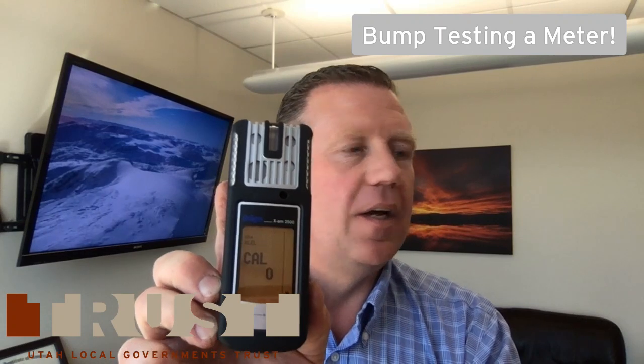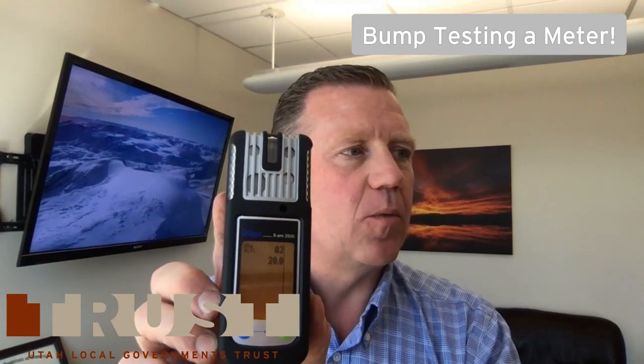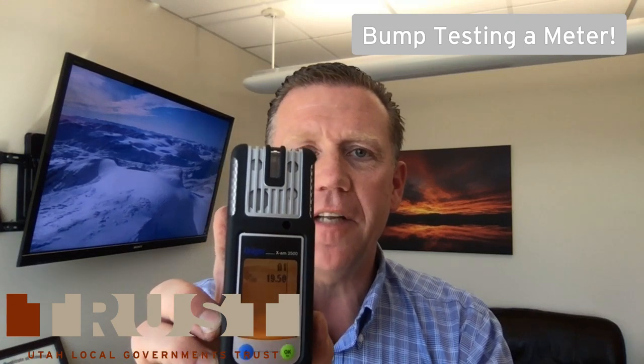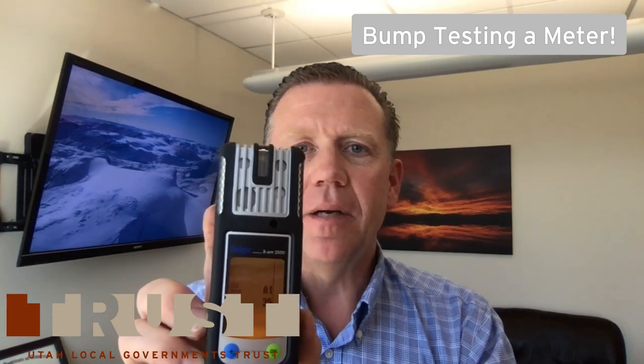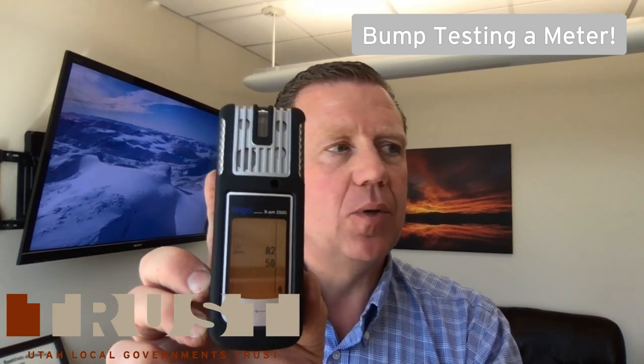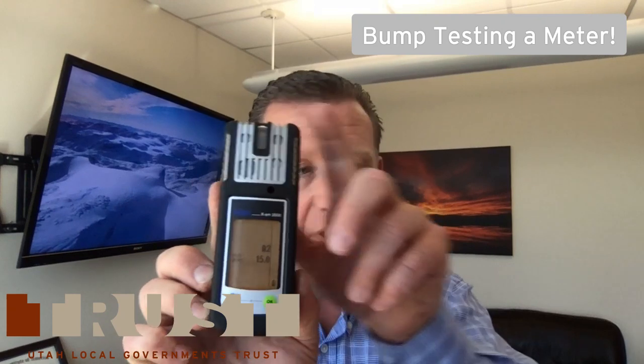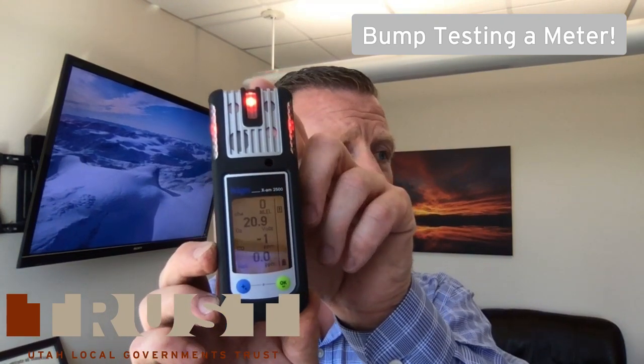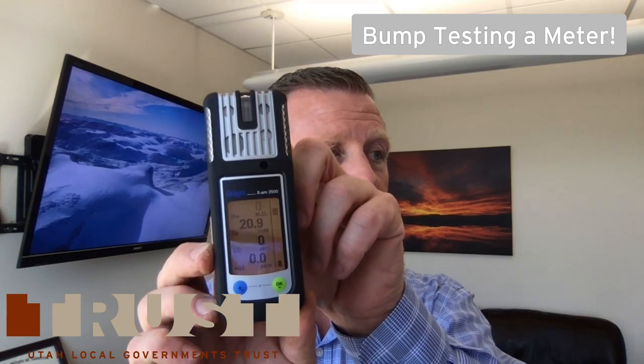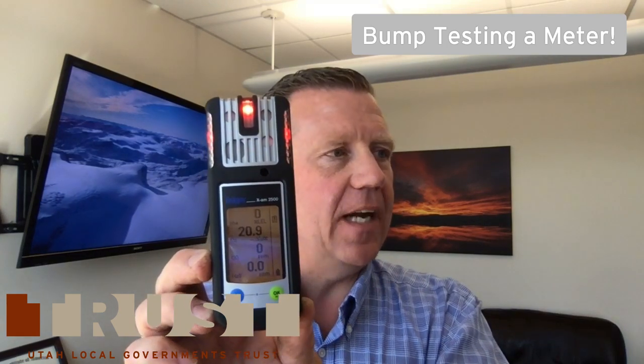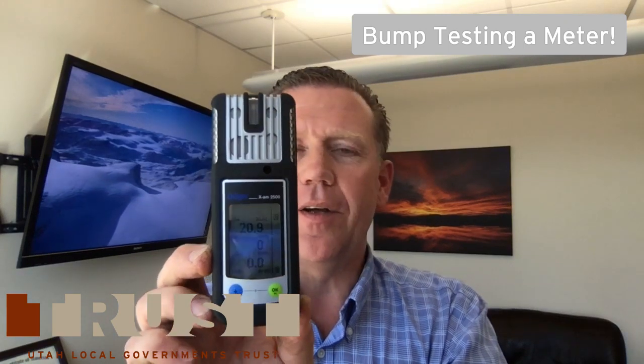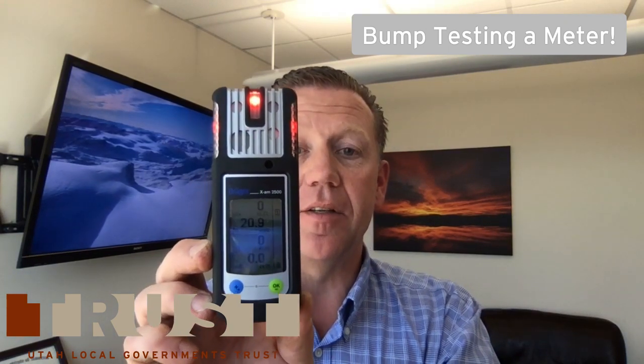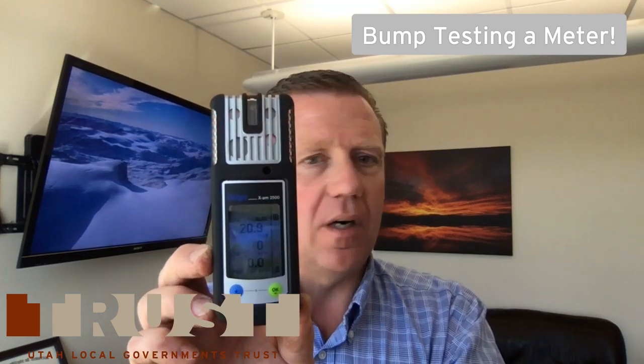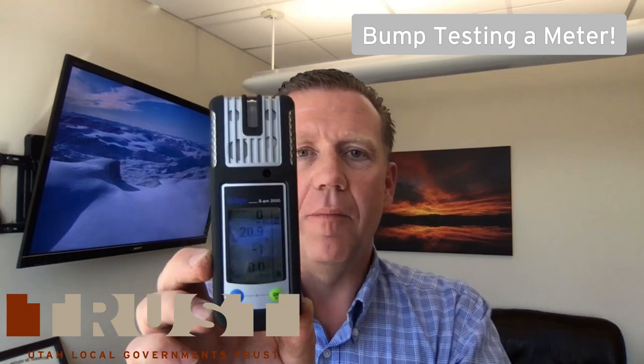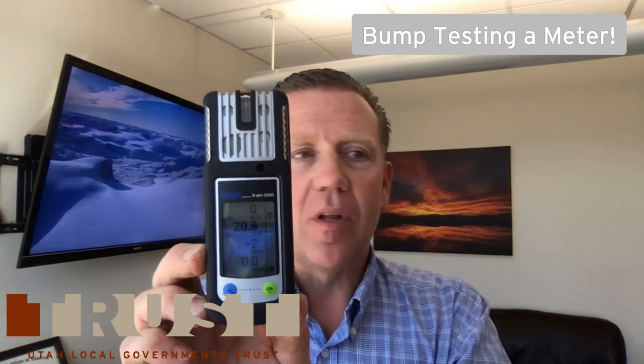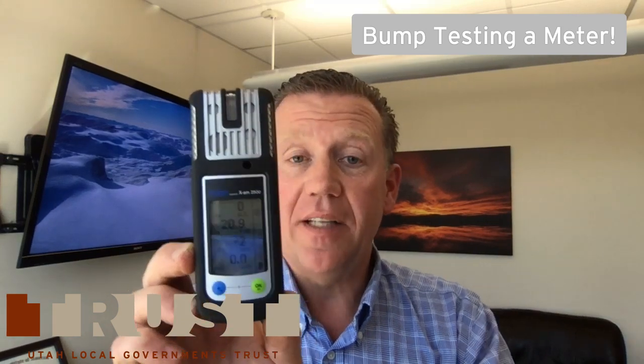It tells me the version and calibration. It tells me the alarms, and I verify that those alarms all make sense for each one of those gases. Once it goes through all of those, it's going to come up and read. We've got one flashing, it's working on something there, and I've also got a little exclamation point there, and that's something I've got to send into the shop. You need to know what each one of those things are, but I can do a bump test on it and make sure that we're good to read for today. So we look at this, I'm reading 20.9% on oxygen, that's exactly where we want it to be.